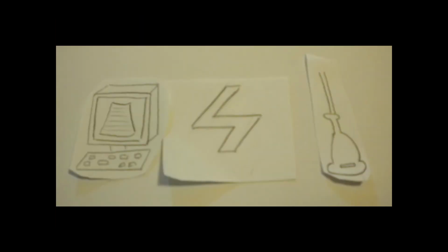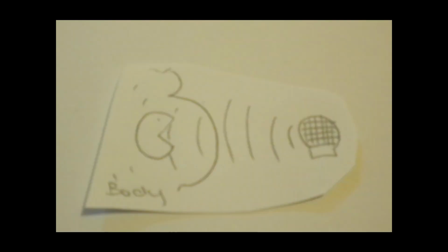Sound waves have high and low pressure areas. The high pressure areas squish the piezoelectric crystal, making one electrode slightly negative, while the low pressure area stretches the crystal, creating a difference in its total electrical charge. The alternating high and low pressure areas in the sound wave go through the transducer and create an alternating current to send back to the computer. This generates an image. Meanwhile, the sound wave is transmitted through a medium in the body.